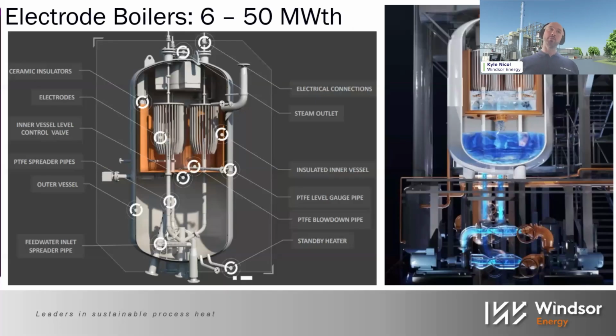Electrode boilers use high voltage, so 11 to 22 kilovolts, and they require a full water demineralization plant to achieve very low conductivity water, which is how they work because the water is the resistive path itself. They range from 6 to 50 megawatts, and they can operate up to 45 bar. Windsor offer the Zander and Ingstrom electrode boilers from Sweden. They have 40 years of experience, and they have over 200 boilers installed.